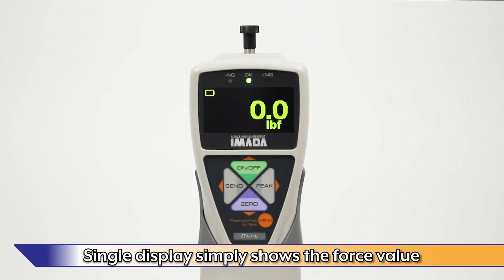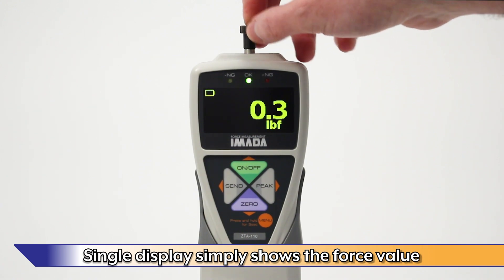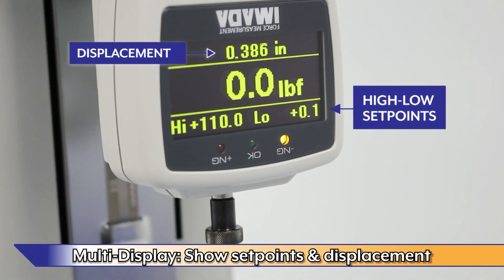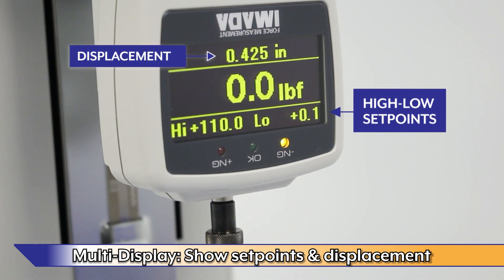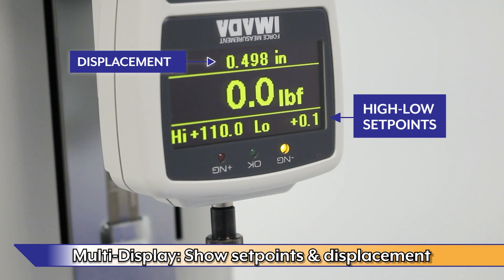Single display simply shows the force value. In multi-display mode, in addition to force, various test conditions can be displayed, such as set points and displacement on gauges mounted to Imada stands with F-A distance meters.